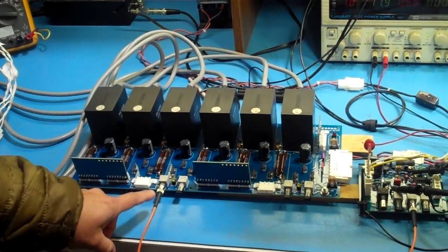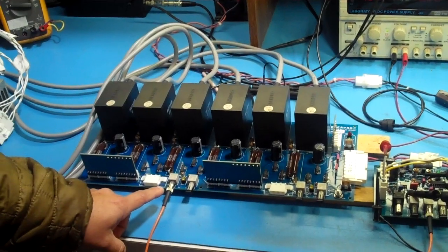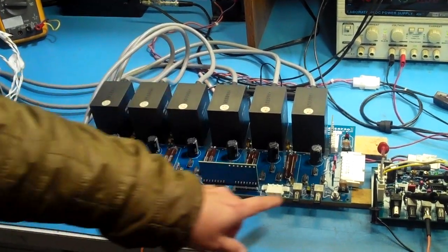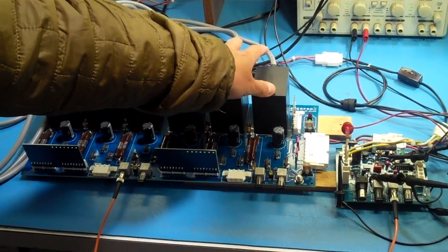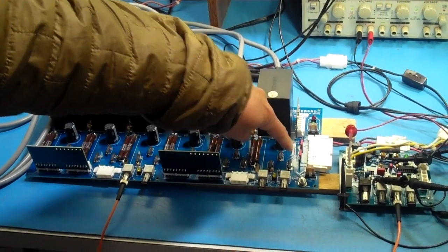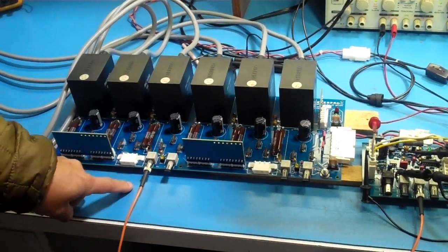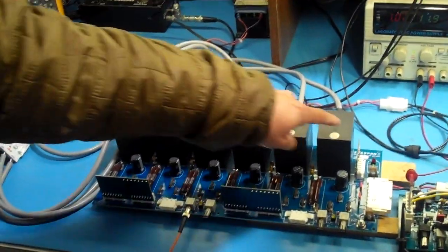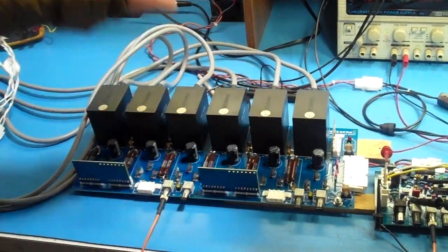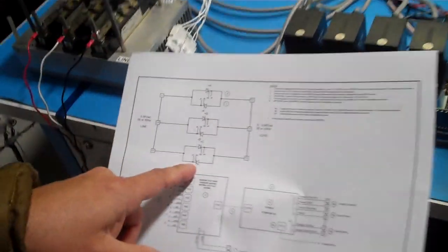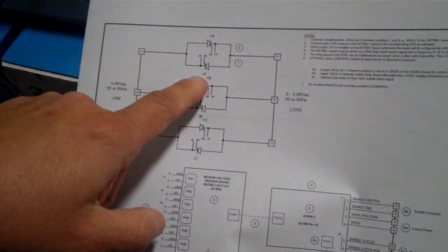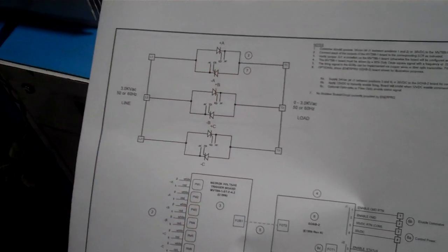we could bring in that input here into this channel that controls these 3 SCRs, or this channel, the receiver, where we control these 3 SCRs. But because we have the GOAB-1 installed, one input, whether we bring it here or here, will send the same output to 6 SCRs. And what we have here is 6 SCRs, 3 dual SCR modules, and anti-parallel.